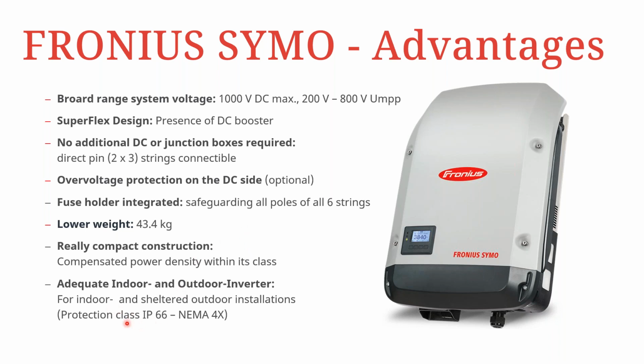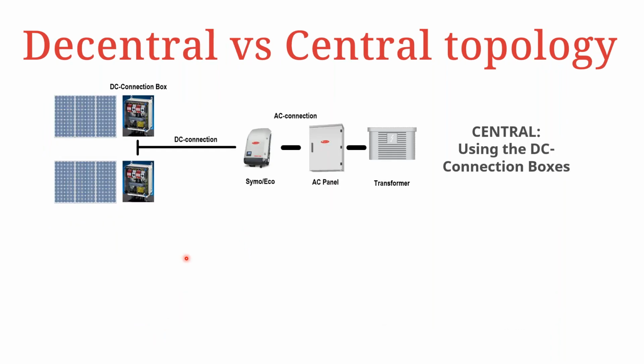And protection class is also IP66 Type 4X. When it comes to the topologies of the systems that can be designed using the Fronius Snap Inverters, the Symo and Eco, we have 2 possibilities. The first option is a centralized design, whereby the inverters are placed next to each other.